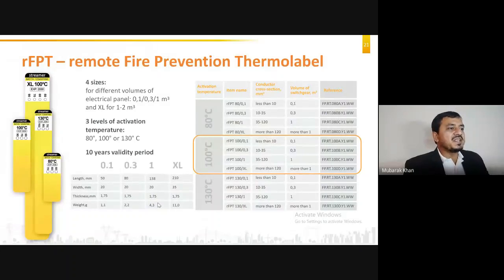These rFPTs are available in various temperatures and various sizes. Temperatures depend on your application, and size depends on the size of the cabinet, because it has to release enough gas to fill that compartment. So depending on the size of the compartment, we have different size stickers, and depending on the conductor diameter, they have different stickers. For smaller conductors we have smaller stickers, for bigger conductors we have bigger stickers.